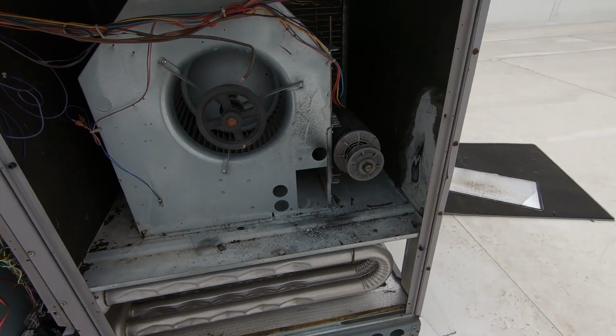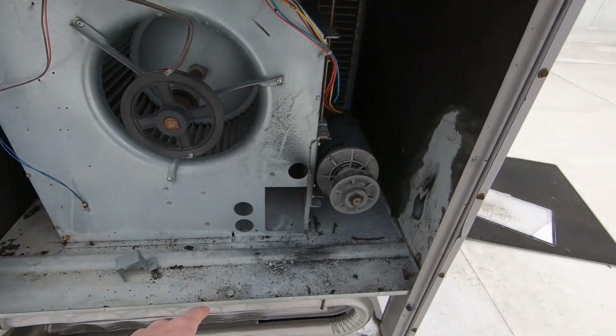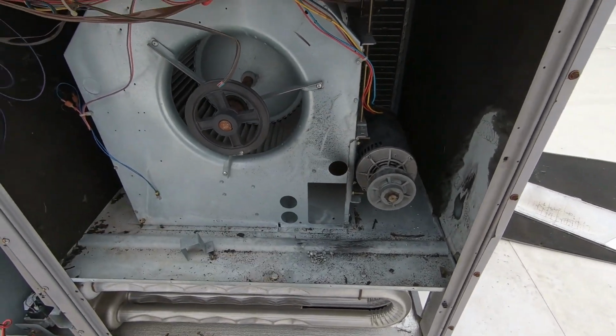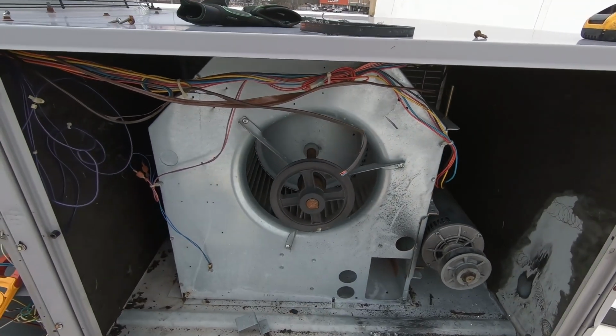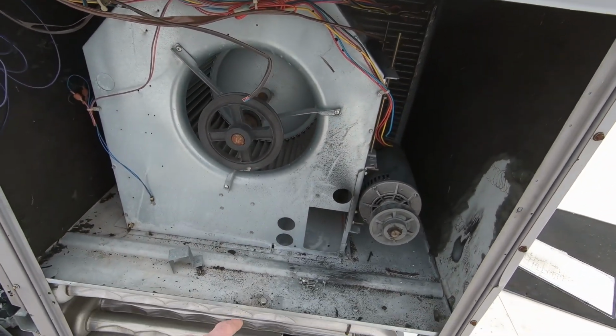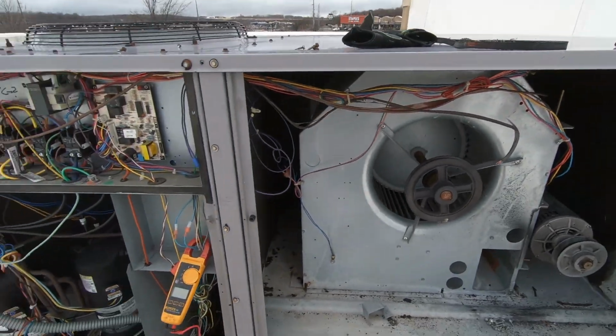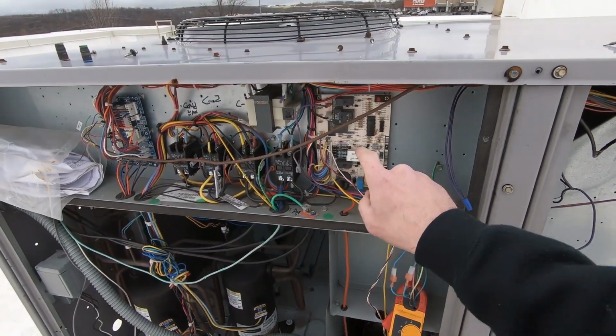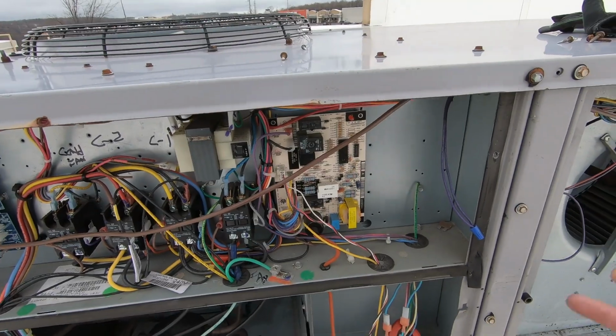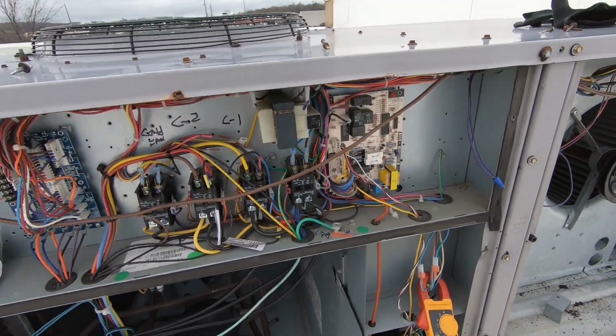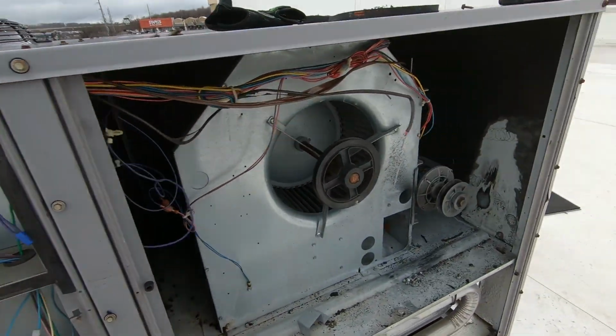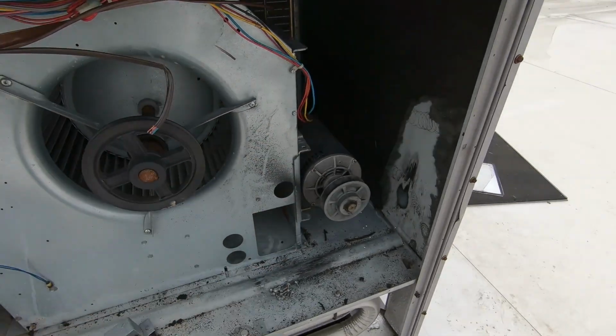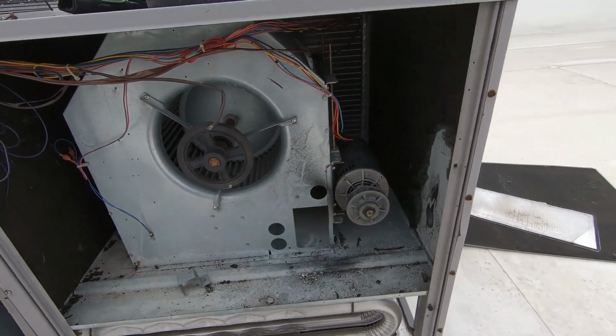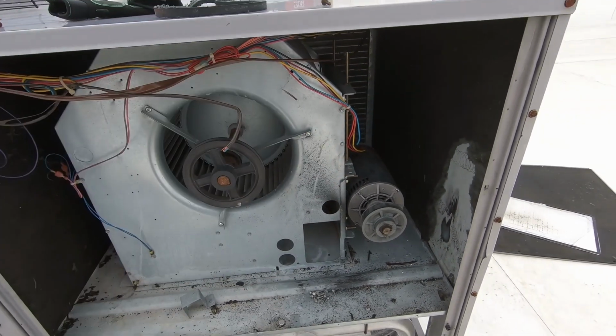The limit was the issue. Had the limit been wired in and the belt got thrown, it would have opened the limit switch, I don't know how many times, 3-5 times, but it would have locked this ignition control board out, and then they would have simply had no heat. It would have been a no heat call. We could have come out, replaced the belt. The blower probably would have still run too, but I have a feeling this motor was running non-stop.